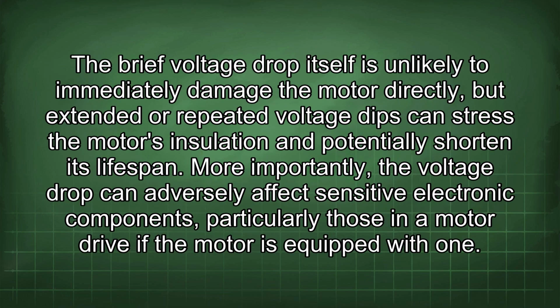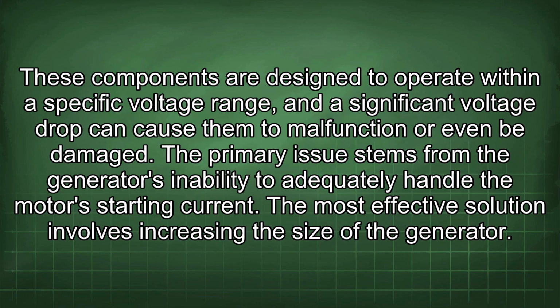The brief voltage drop itself is unlikely to immediately damage the motor directly, but extended or repeated voltage dips can stress the motor's insulation and potentially shorten its lifespan. More importantly, the voltage drop could adversely affect sensitive electronic components, particularly those in a motor drive if the motor is equipped with one. These components are designed to operate within a specific voltage range, and a significant voltage drop can cause them to malfunction or even be damaged.